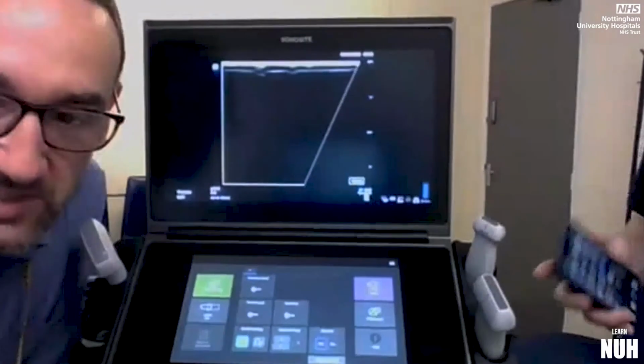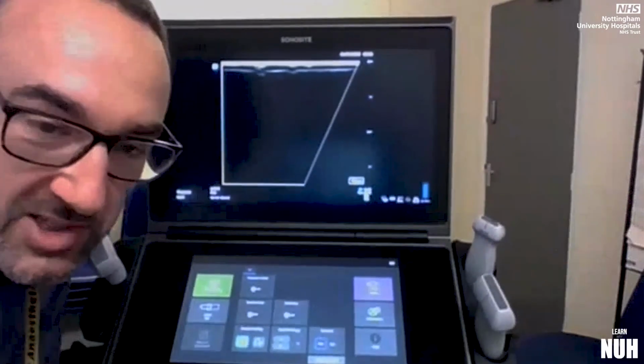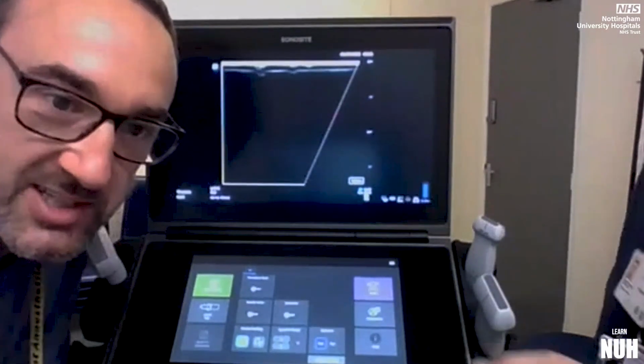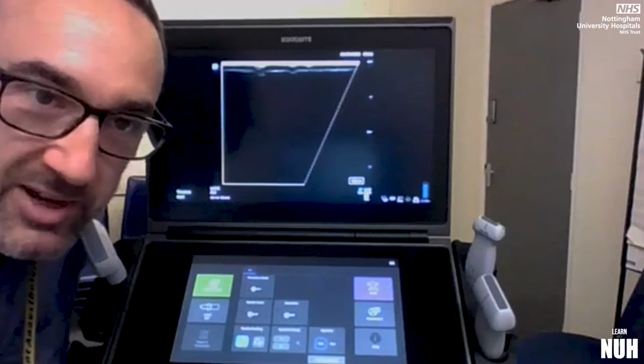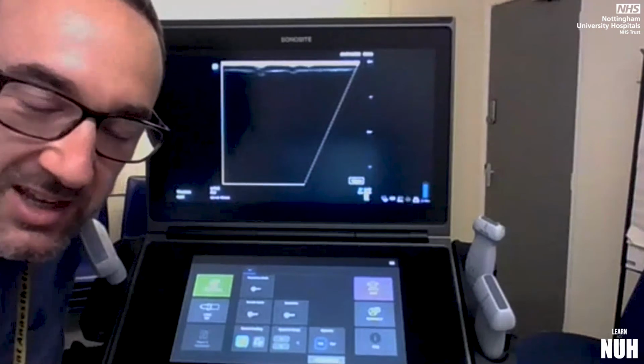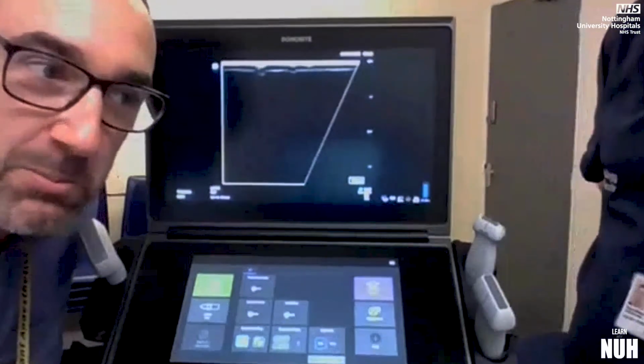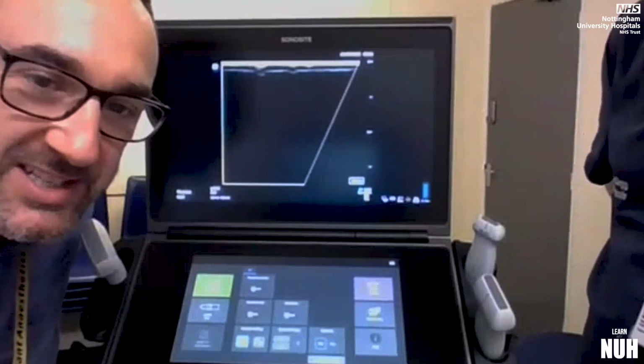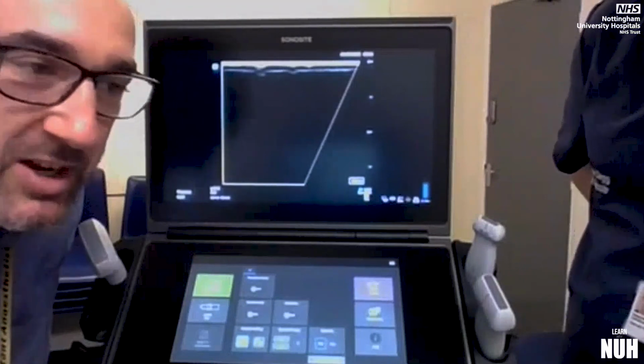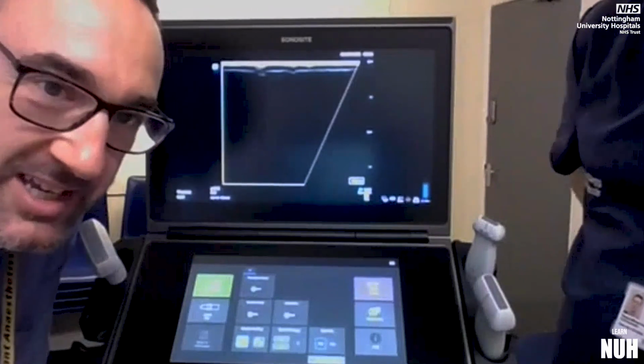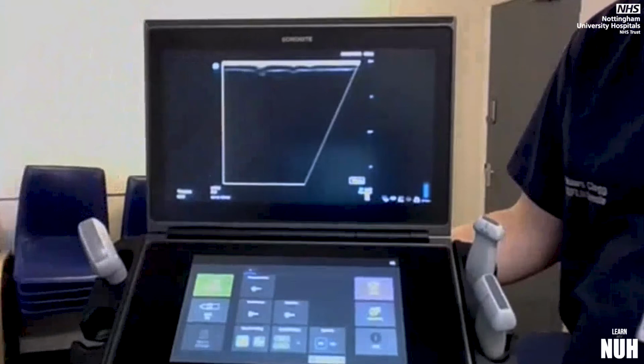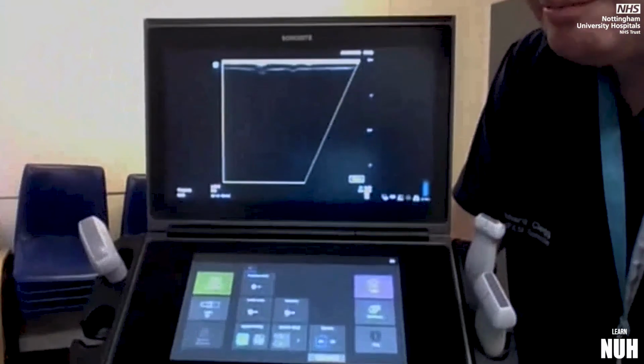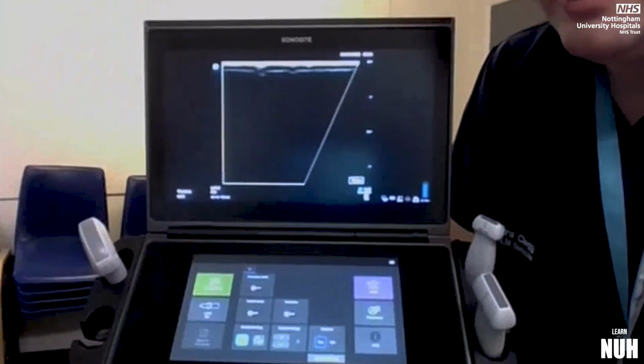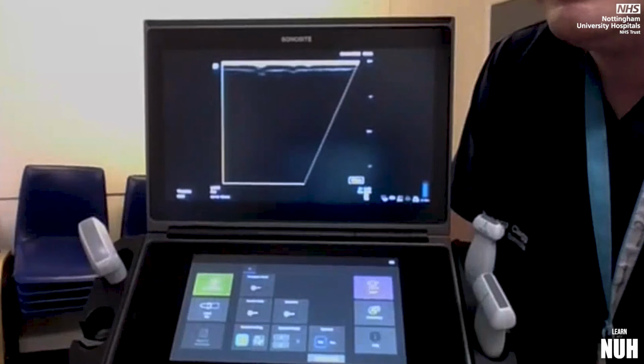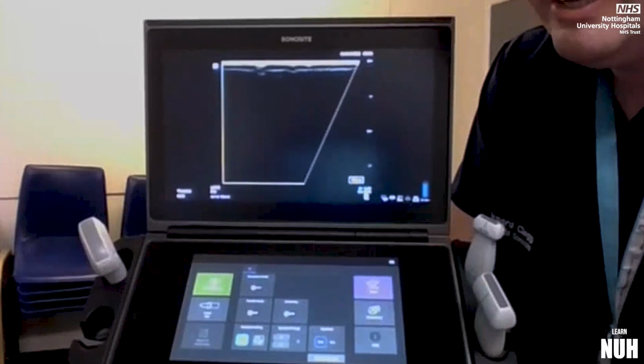There's one thing that Sonosites can't do, and that's cope with having needles stuck into the head of the probe. So be very, very careful when you put the needle through the skin. If you're at all worried about it, pull the probe off as you put the needle into the skin and then put the probe back down, because we've lost loads of probes from people sticking needles into the tip of them. Please don't. So stab people, not probes. They're about £5,000 each if you needed to replace them out of warranty.